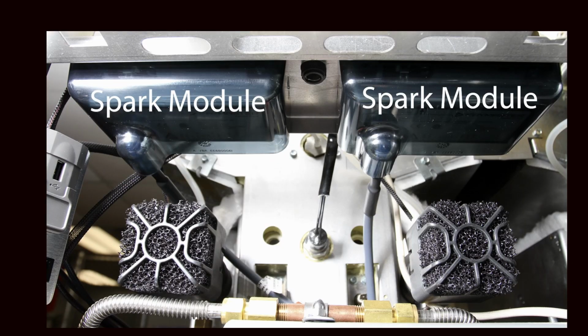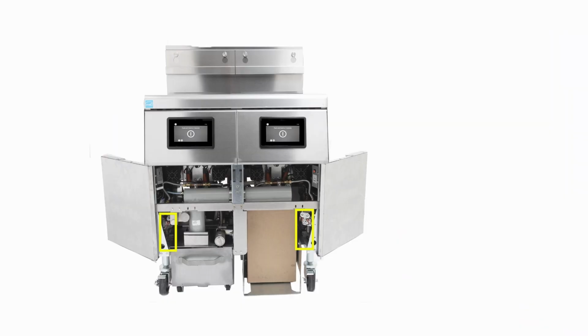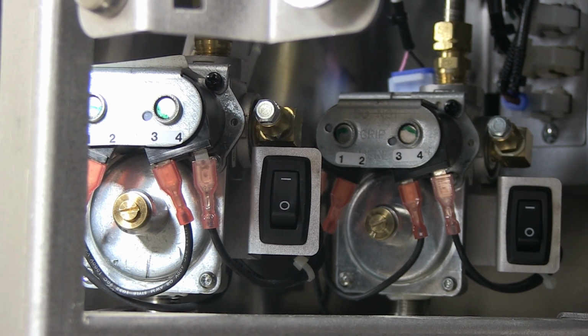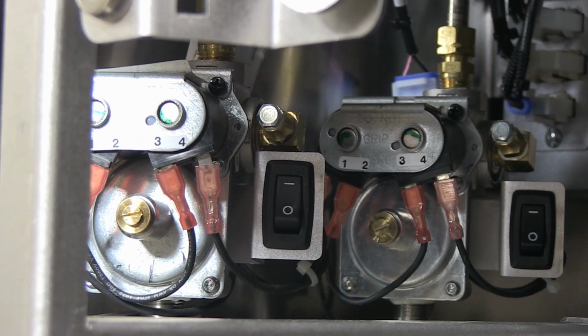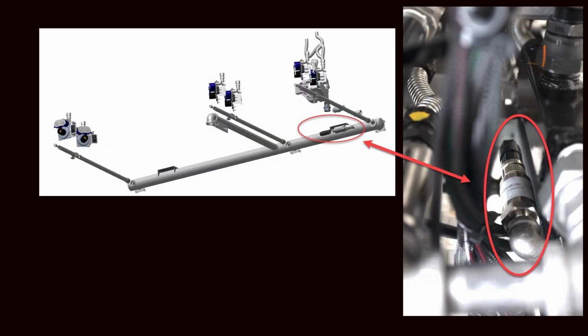Also in the upper cabinet, under translucent protective covers, are the 24-volt DC spark modules. Lower in the cabinet are 24-volt DC gas valves, one for each burner. The valves sit on a manifold that includes a pressure sensor, which monitors and reports the incoming gas pressure. The sensor can be seen here in the drawing and in the cabinet.